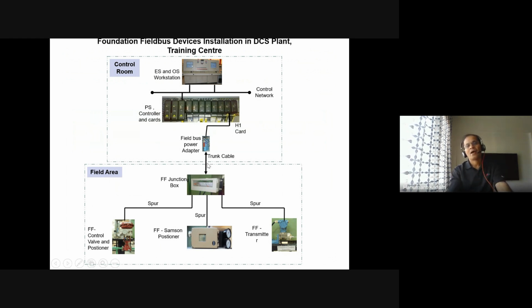Earlier we needed a power supply adapter installed in the DCS cabinet itself, in the control room system cabinet. But now the power is inbuilt in the card. This card is the H1 card - H1 meaning the H1 protocol in the field bus - and for interfacing with the existing DCS, this card is used, normally called the Foundation Fieldbus Interface Card or H1 card, the Foundation Fieldbus protocol-based devices interface card.